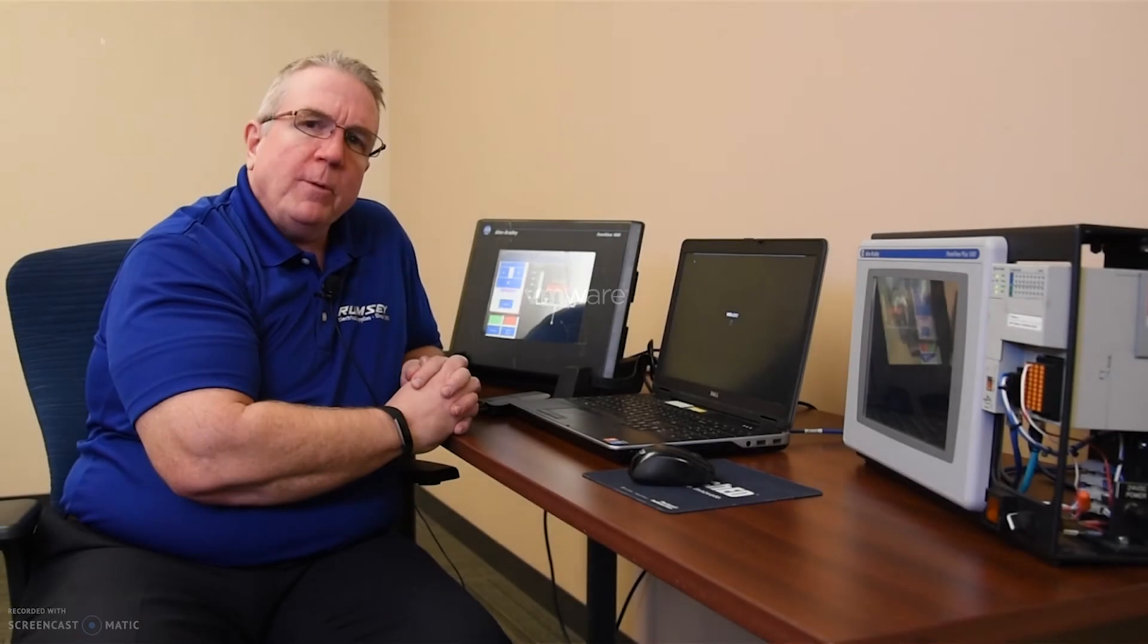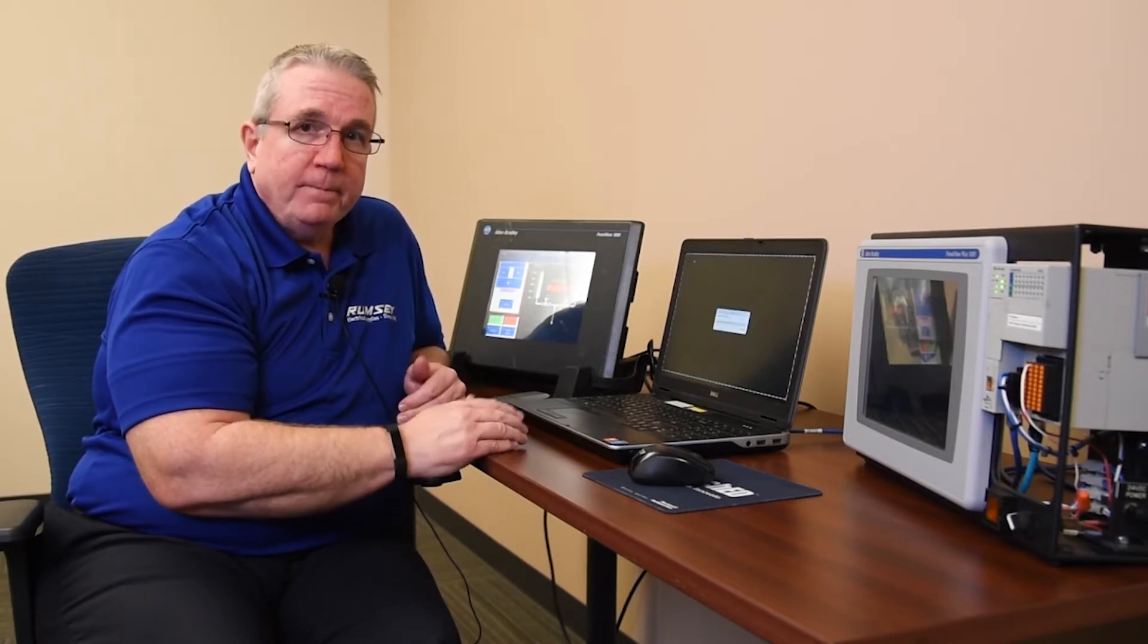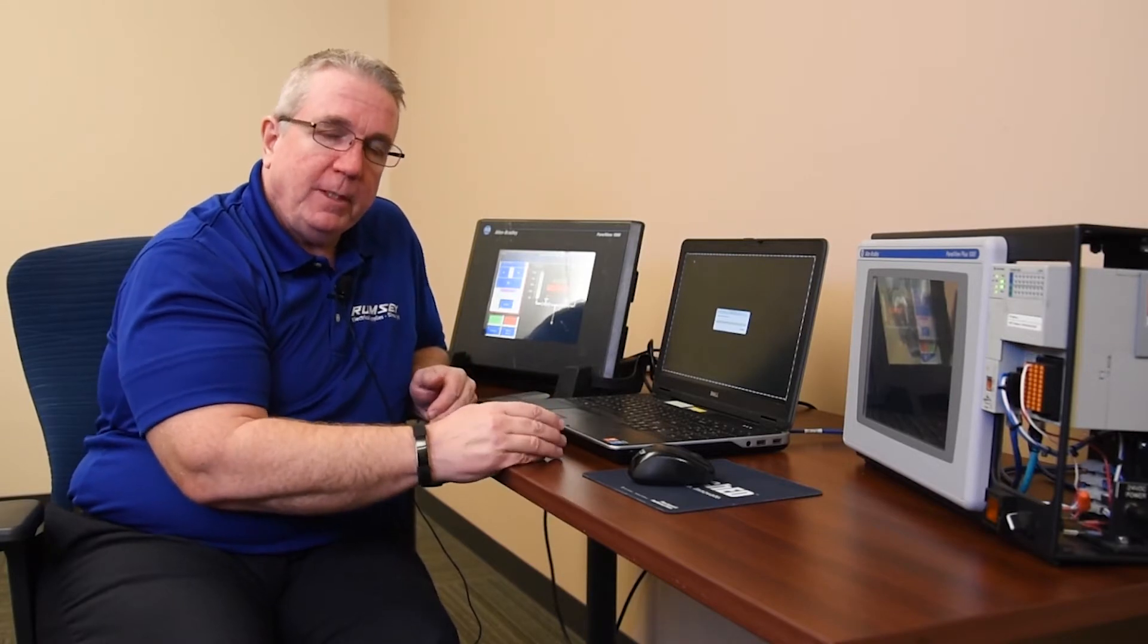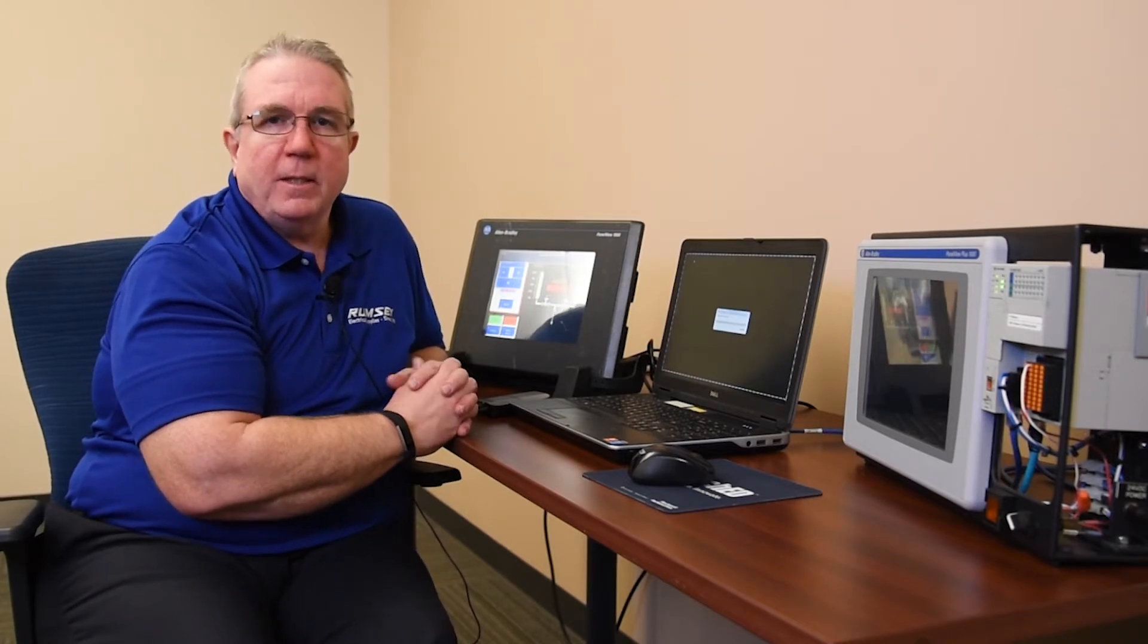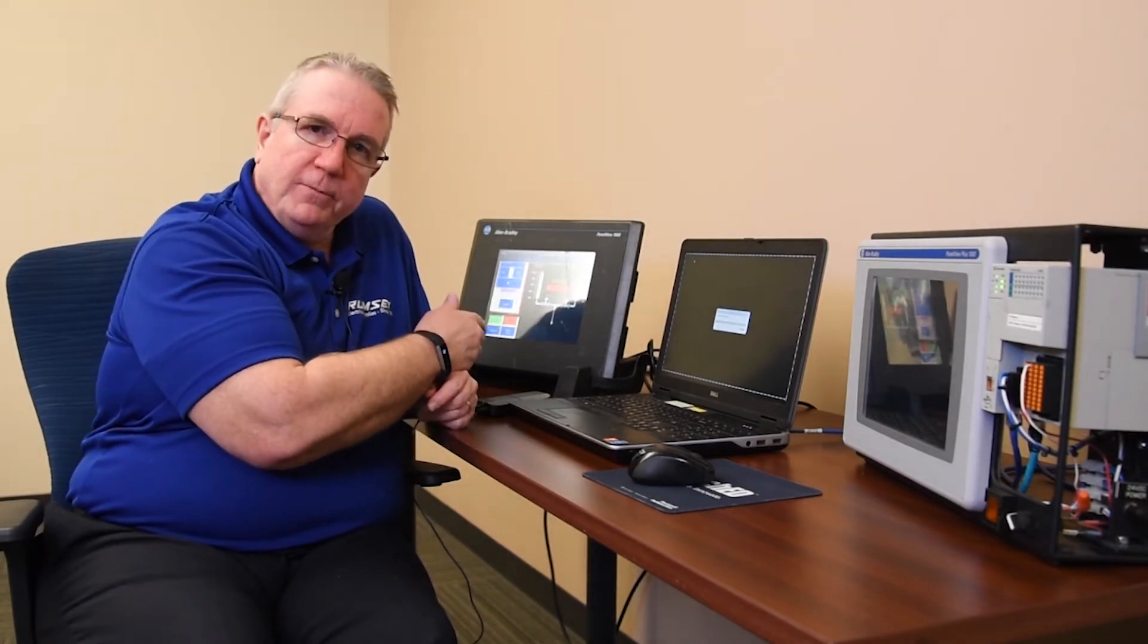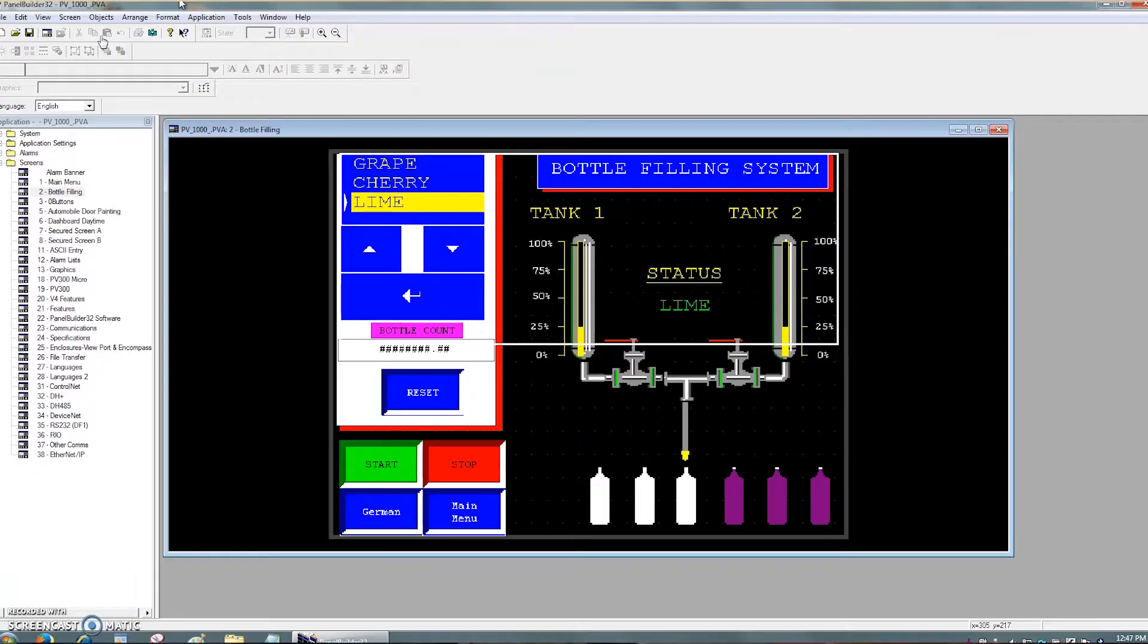And you're like, OK, you didn't show me what the old project looks like. Well, that's no problem. I actually have it right here in PanelBuilder32 to show you. Now, PanelBuilder32, if you do have a copy of it, only runs in a 32-bit environment. Originally from Windows XP, I've had very good success running it in Windows 7 32-bit, but I have not been able to run it in Windows 7 64-bit and certainly not a Windows 10 environment. So keep all that in mind if you're going to try to use the old software to upload it from the panel view or if you want to manipulate it some way before you do the migration.